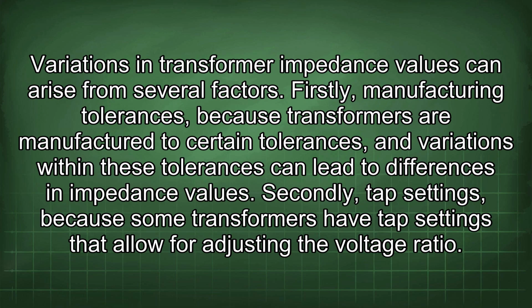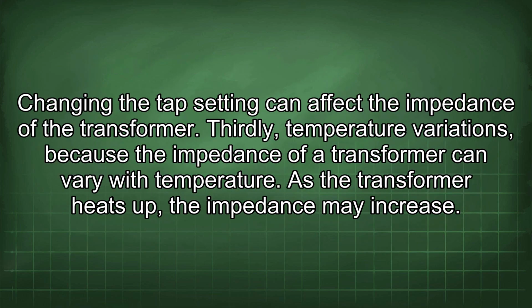Variations in transformer impedance values can arise from several factors. Firstly, manufacturing tolerances, because transformers are manufactured to certain tolerances, and variations within these tolerances can lead to differences in impedance values. Secondly, tap settings, because some transformers have tap settings that allow for adjusting the voltage ratio. Changing the tap setting can affect the impedance of the transformer. Thirdly, temperature variations, because the impedance of a transformer can vary with temperature. As the transformer heats up, the impedance may increase.